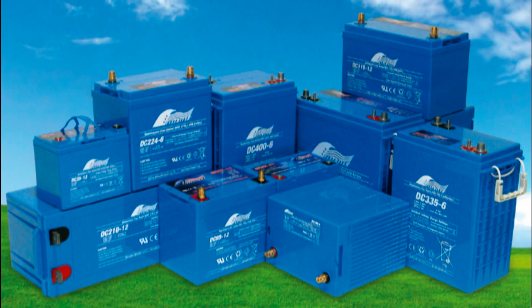AGM batteries won't leak, explode, or gas out like wet cells. They have a catalyst in the casing that recombines the hydrogen and oxygen molecules back into water, which prevents them from gassing or exploding. You never add water to AGM batteries. But the bottom line is that chemically, wet cells and AGM batteries are identical, and they require certain charging and monitoring — that will be covered in another video. My opinion: stick with wet cells, genuine deep cycle batteries, or possibly AGMs. I'll have a better opinion on AGMs in another year or two.